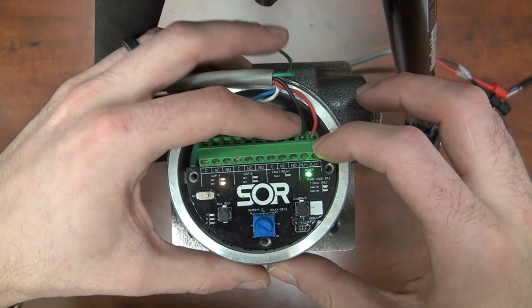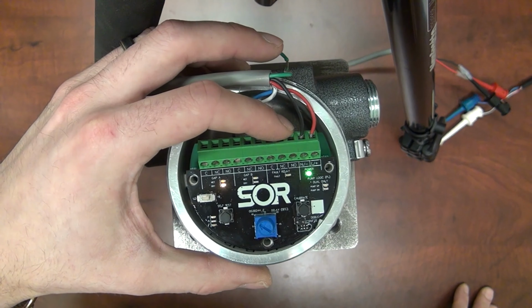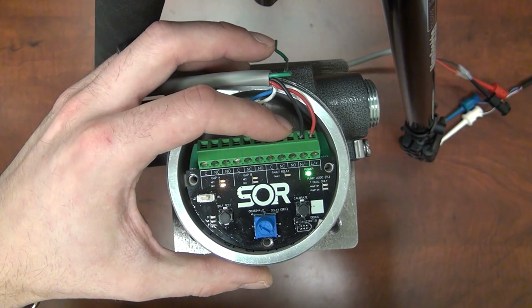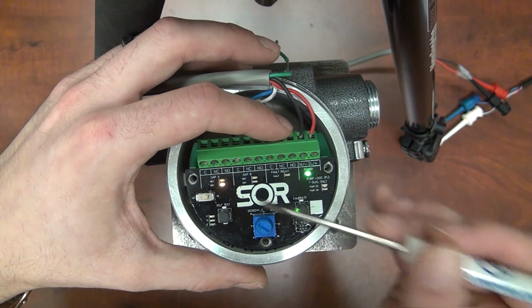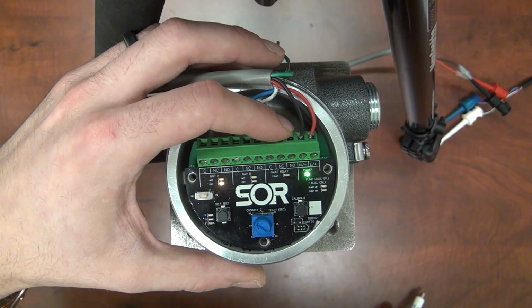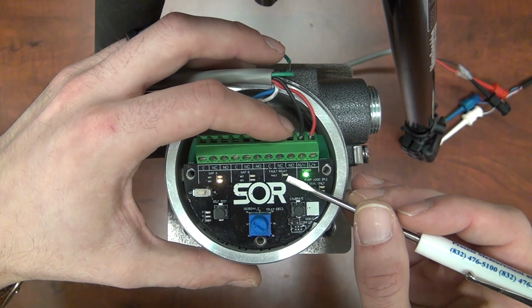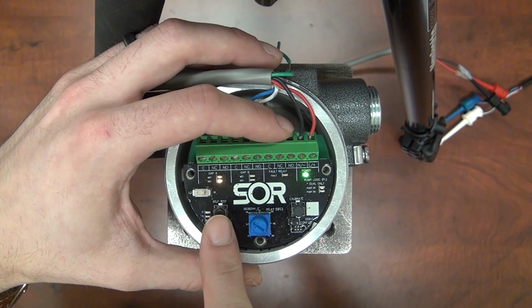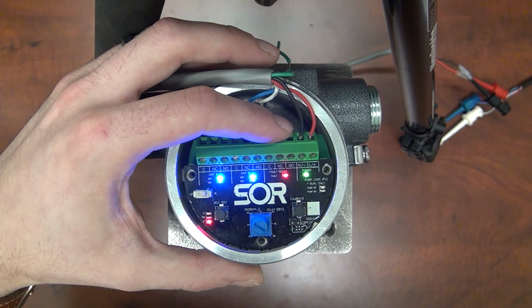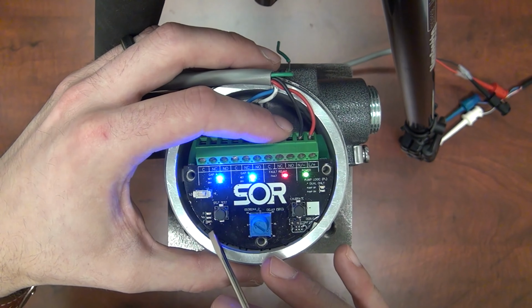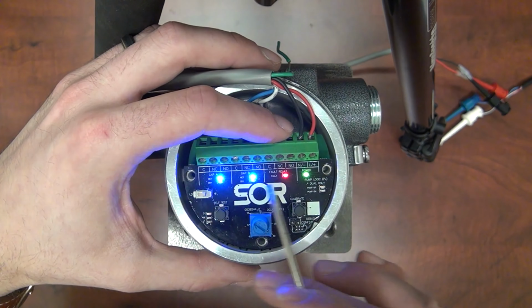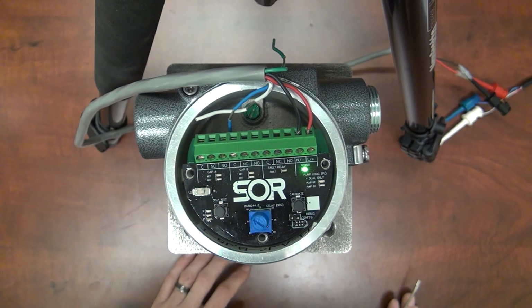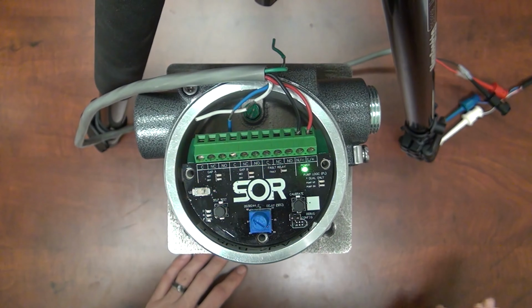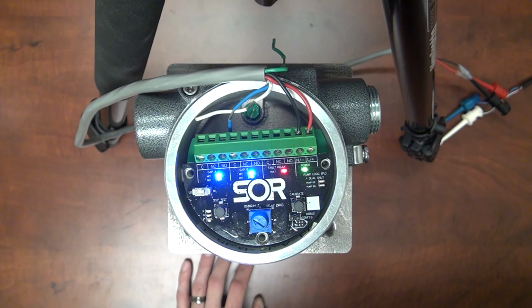In this case, with the T cable disconnected, we'll see the gap A wet LED up here flashing, and then the fault LED here flashing red. When I press the self-test button, we'll see that occur. It's flashing red, indicating there's a fault state, and these here are flashing. This indicates the T cable is disconnected. Turn off power to the device.